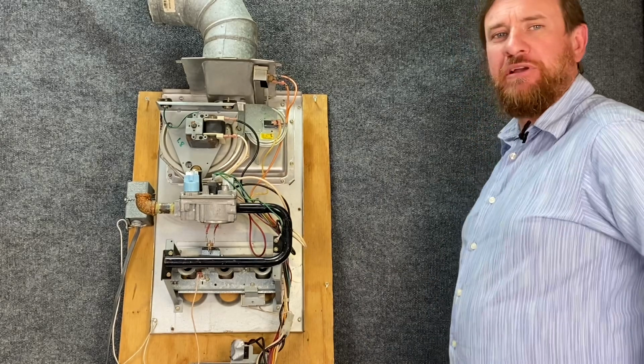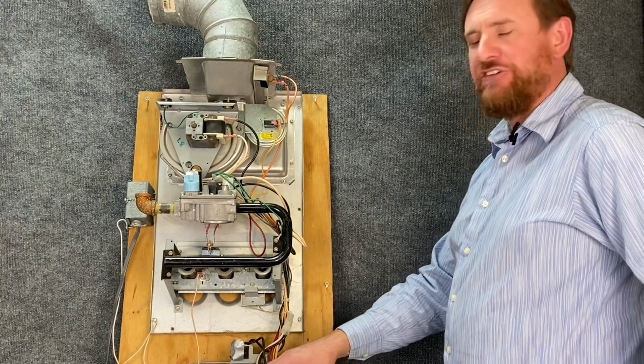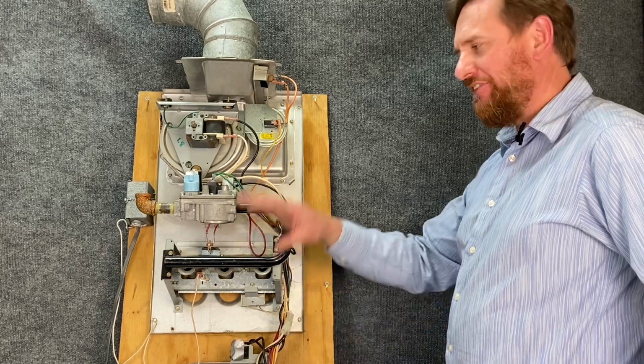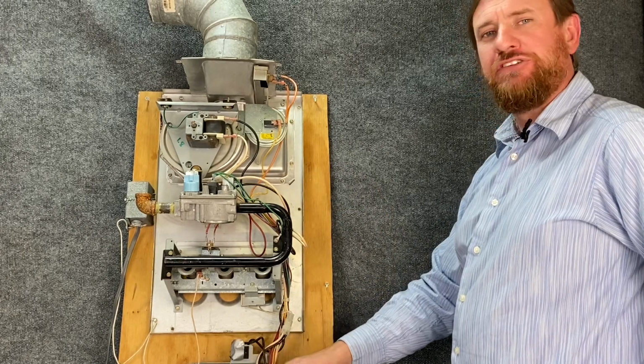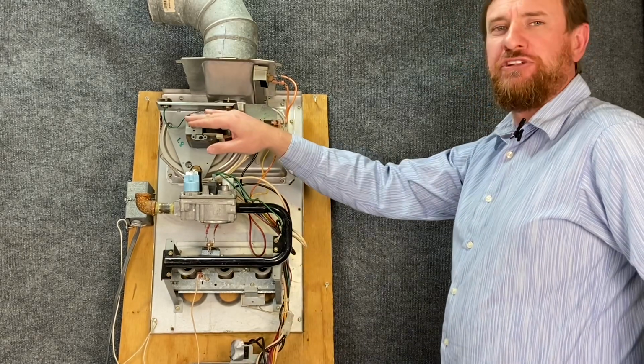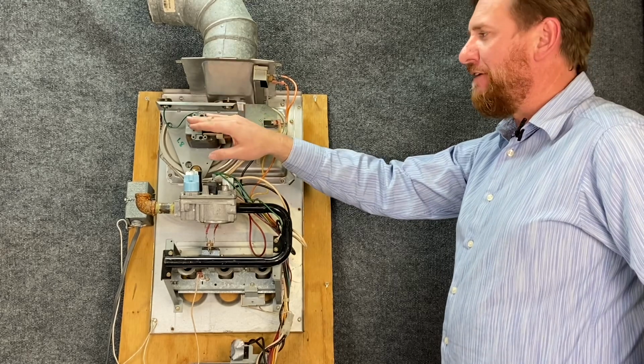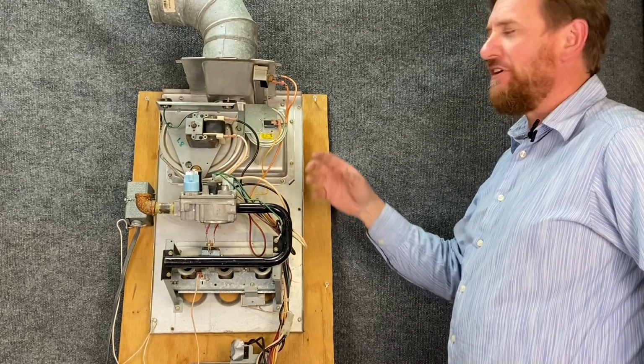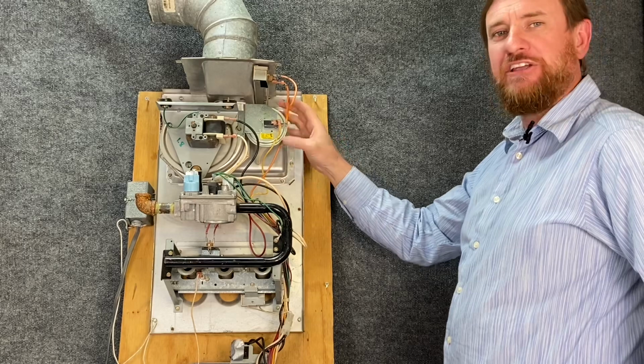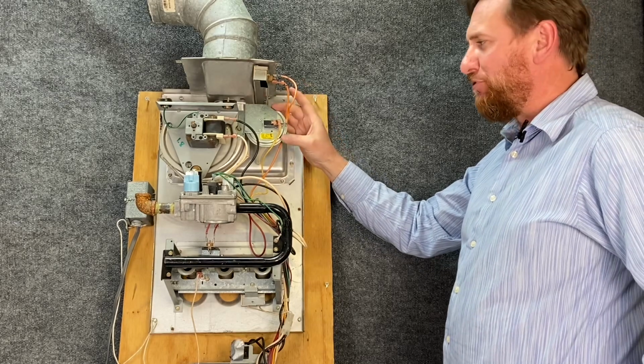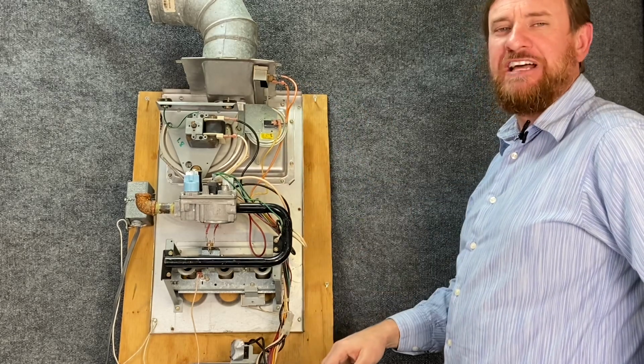The sequence of operation: the thermostat calls for heat and sends 24 volts to the IFC. The IFC does a safety check. The IFC closes a relay and sends 120 volts to our inducer fan motor. Our inducer fan motor pulls a draft through the heat exchanger. It also pulls a vacuum to our pressure switch. Our pressure switch closes and sends 24 volts to the IFC.